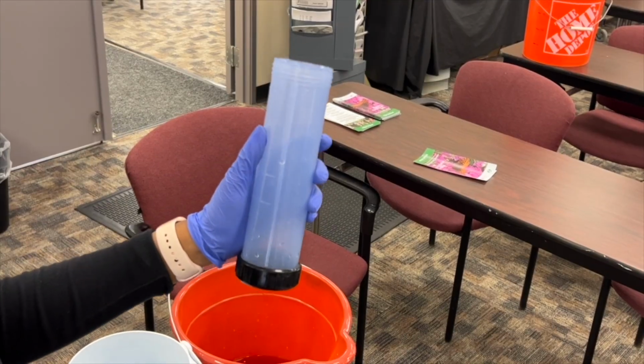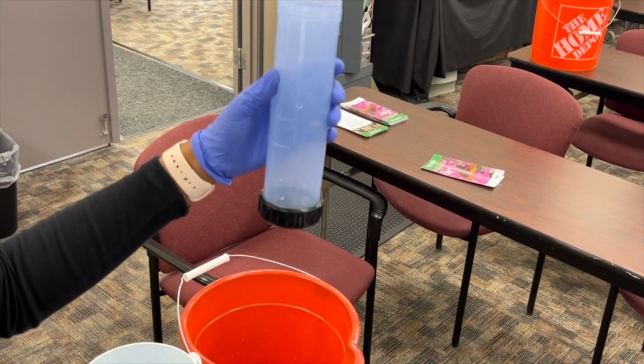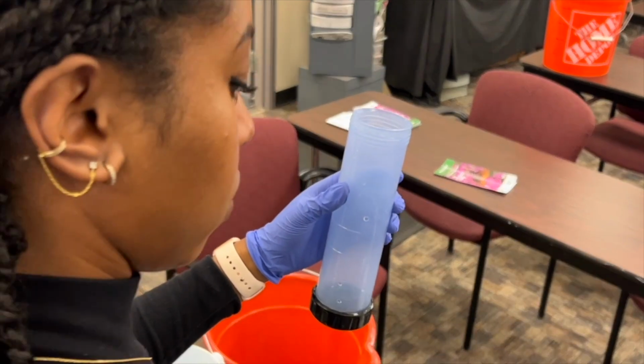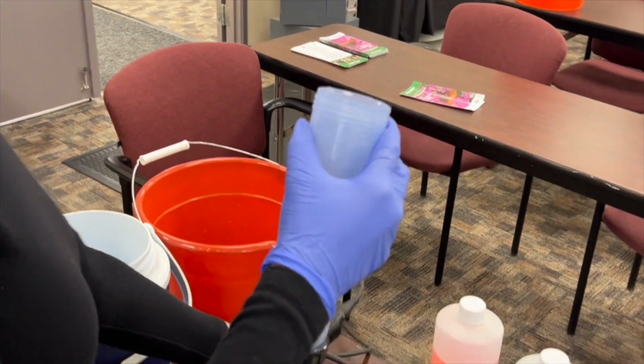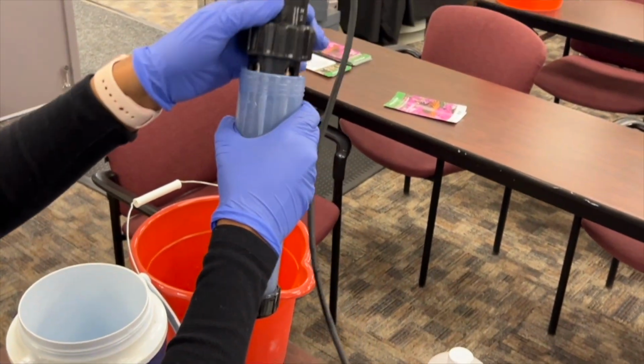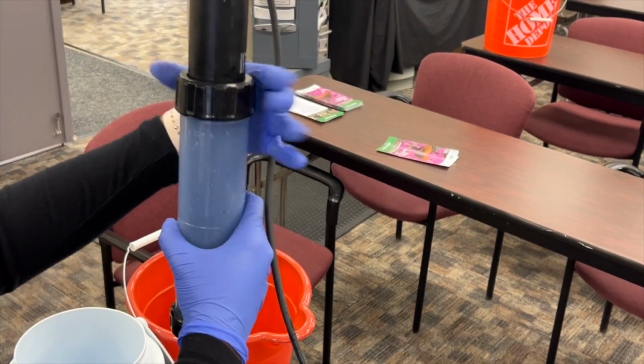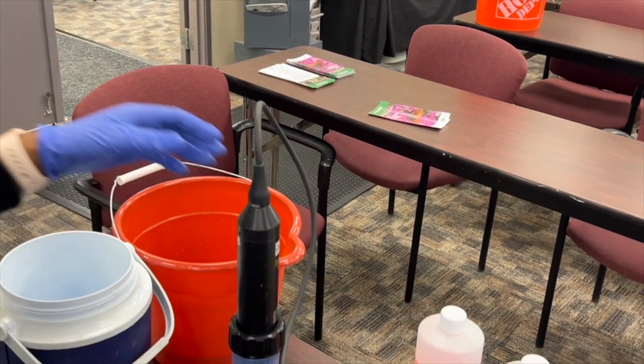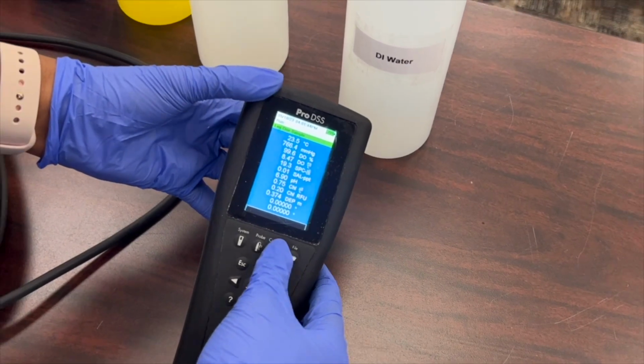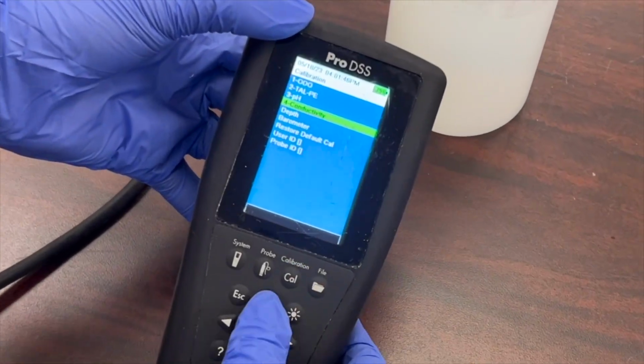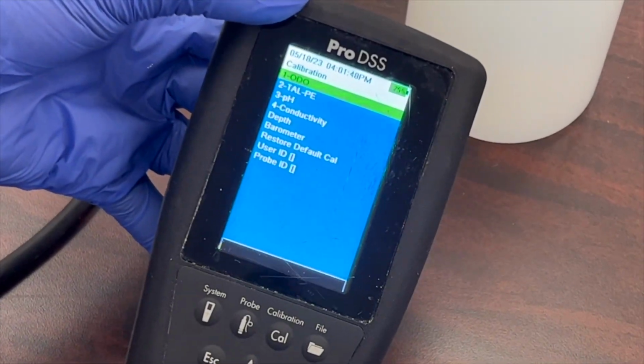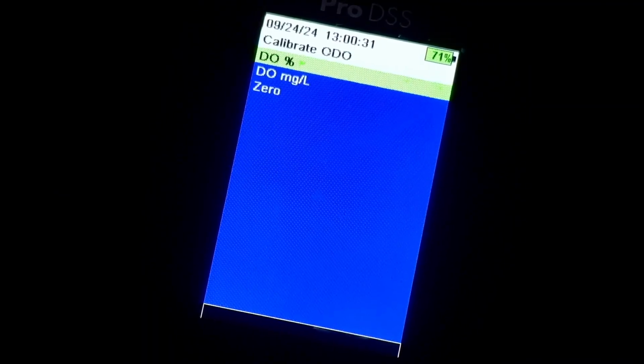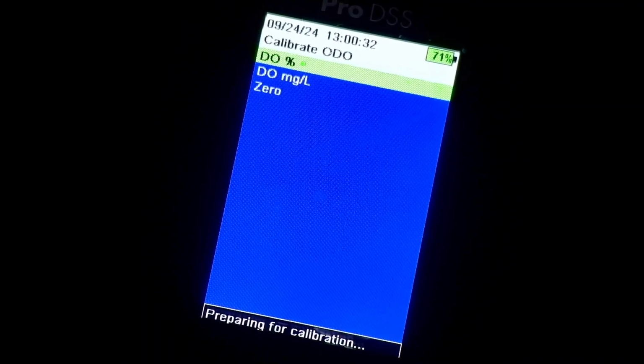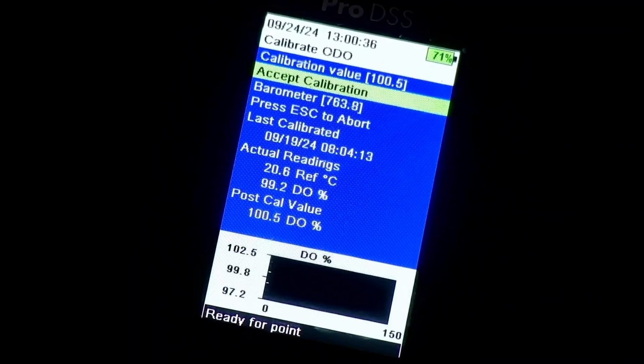As always, discard the buffer from the calibration cup and then rinse it along with the sensors. Fill the calibration cup up with about half an inch of fresh water, insert the sonde, and partially tighten the retaining nut to allow airflow. Wait for 5 to 15 minutes while the air becomes saturated with water. Then, press the cal button and select ODO/DO. Select DO percentage and wait for the numbers to stabilize.